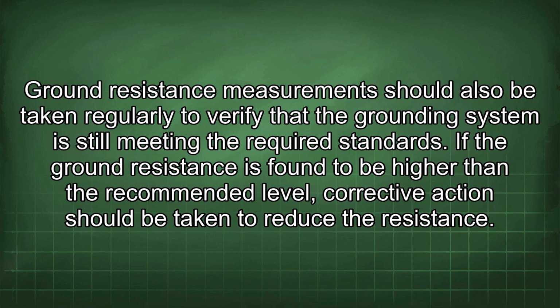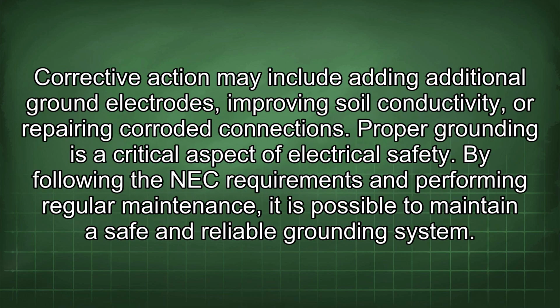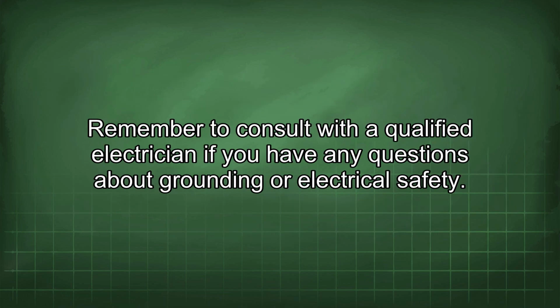If the ground resistance is found to be higher than the recommended level, corrective action should be taken to reduce the resistance. Corrective action may include adding additional ground electrodes, improving soil conductivity, or repairing corroded connections. Proper grounding is a critical aspect of electrical safety. By following the NEC requirements and performing regular maintenance, it is possible to maintain a safe and reliable grounding system. Remember to consult with a qualified electrician if you have any questions about grounding or electrical safety.